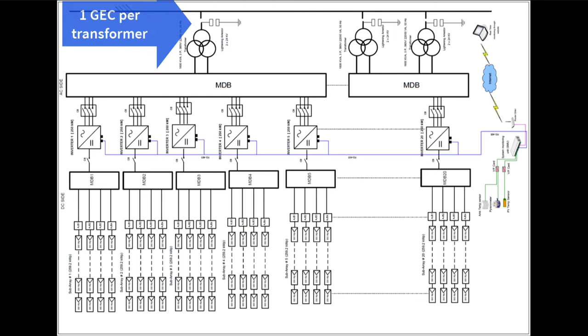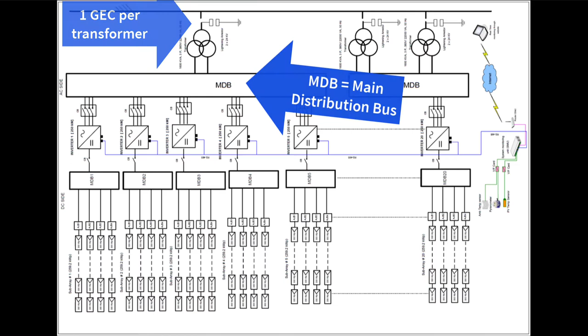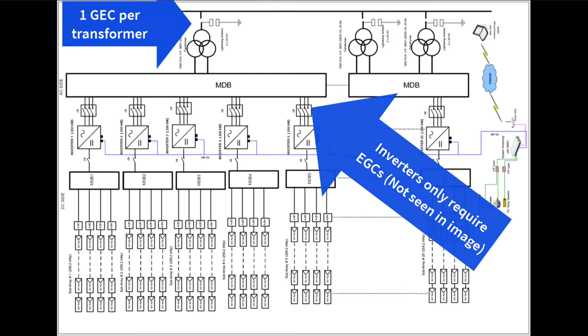How's that going to happen too? It'd just be like just for smaller inverters too, right? Yeah, so let's say you had a main service switchboard or something like that, some big piece of equipment. Switch gear that's going to take overcurrent protection for each inverter. Right. So then there would be overcurrent protection. In that case, you have overcurrent protection for each of the 4 inverters at that location. And that service equipment would be connected to the grounding electrode conductor. The individual inverters would not be. The individual inverters are just going to bring their equipment grounding conductor to that point.